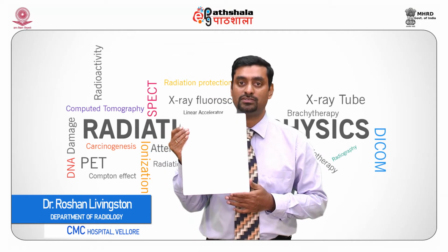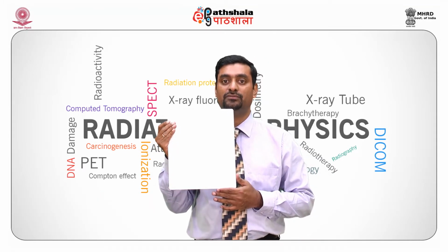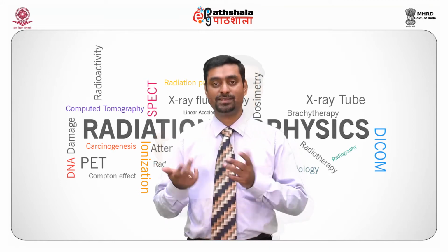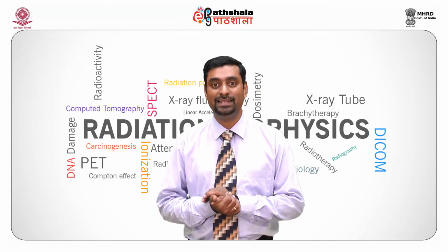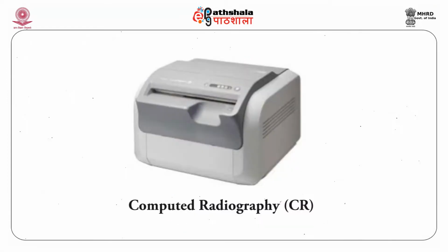It is said that about 25% of loss can happen in the IP plate if it's not read within 10 minutes to 8 hours. This phenomenon is called fading. This IP plate, which now contains the invisible latent image, is fed into a CR reader.